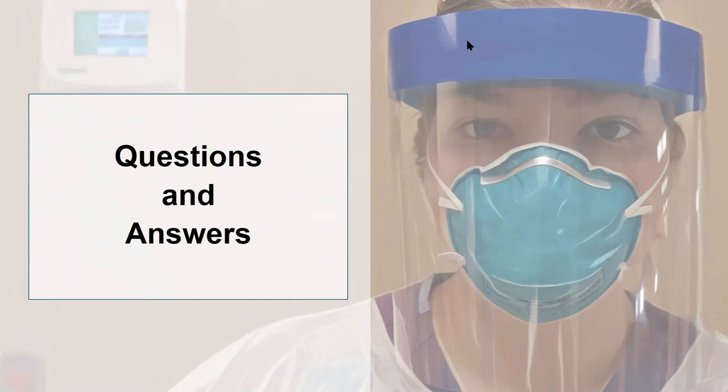The next question: how were you able to maintain your ACPH while also achieving negativity? The person noted they had to dampen supply in order to increase exhaust, which compromised the ACPH. Michael responded: they didn't even have to work with their balancing on the supply — they were just trying to exhaust more air out of the room than was coming in through supply. By using portable HEPA filters with a variable speed fan, they were able to increase the CFMs until the Magnehelic gauge showed that directional airflow changed from positive to negative.